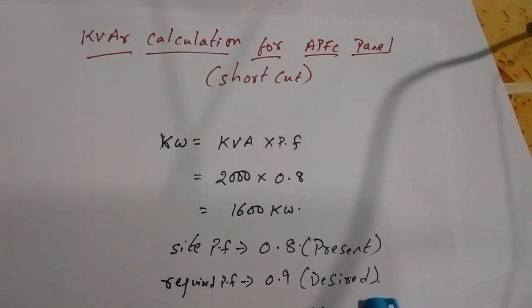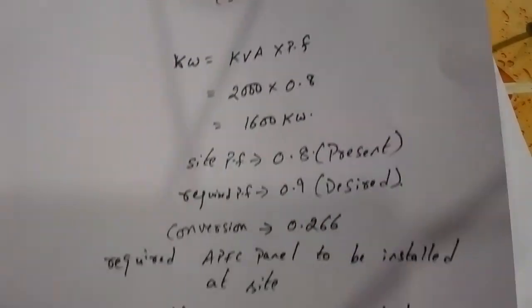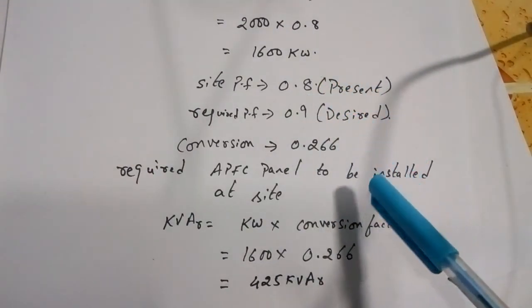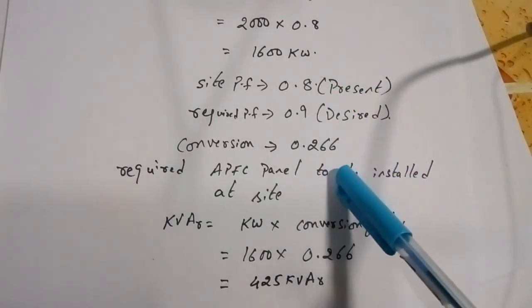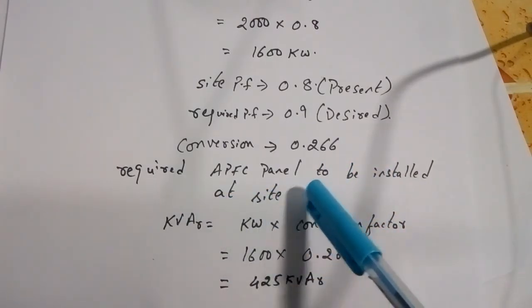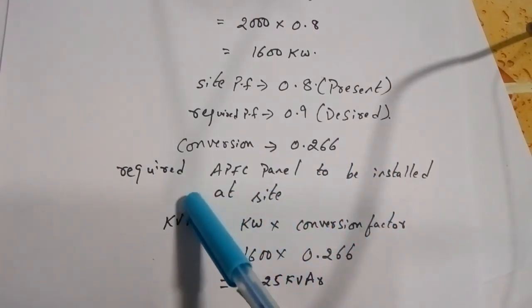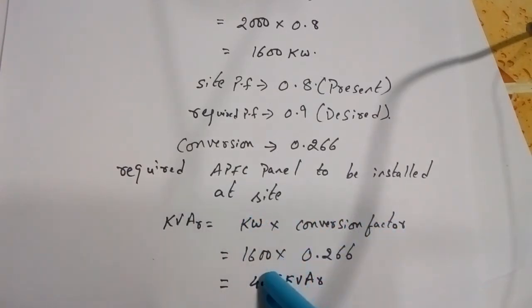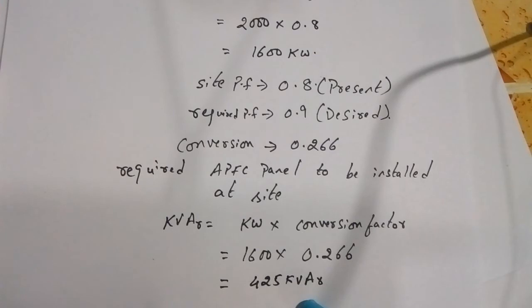The required or desired power factor is 0.9. The conversion factor to convert to the desired power factor of 0.9 is 0.266. So the required APFC panel to be installed at site is: kVAR equals kilowatt into conversion factor, that is 1600 into 0.266, which equals 425 kVAR.